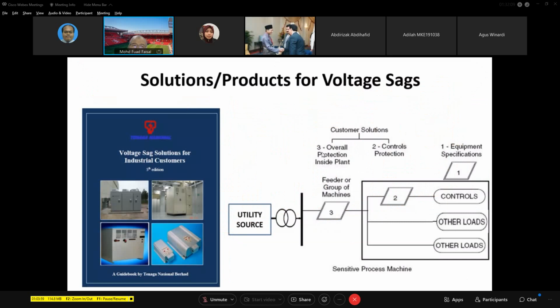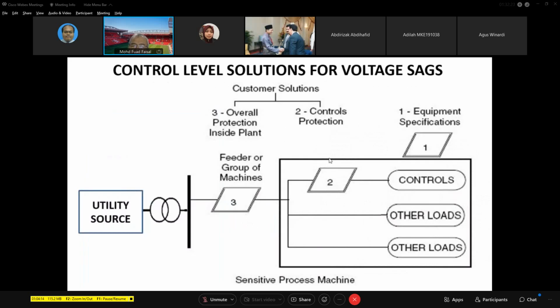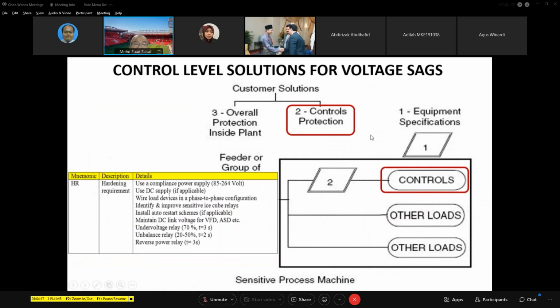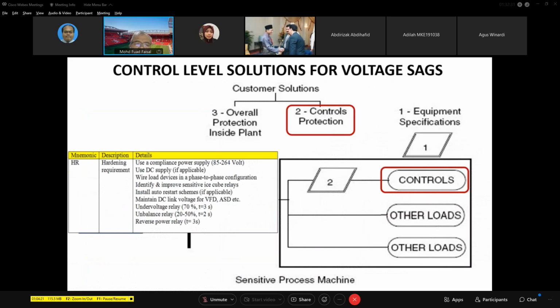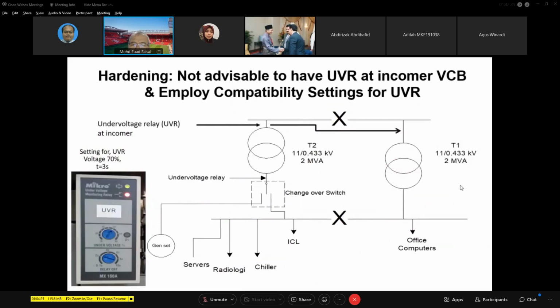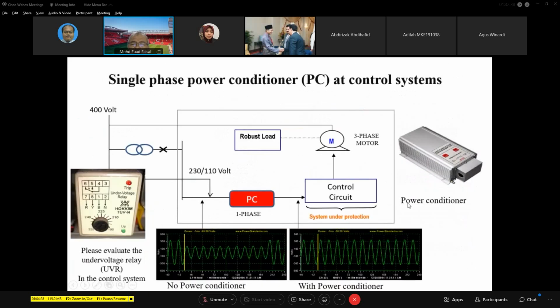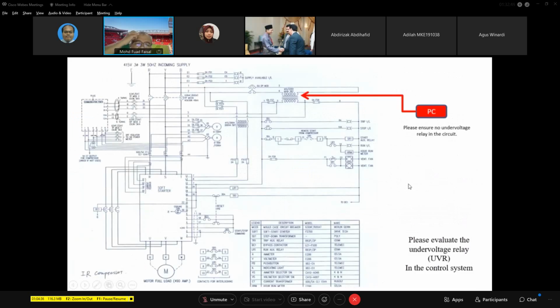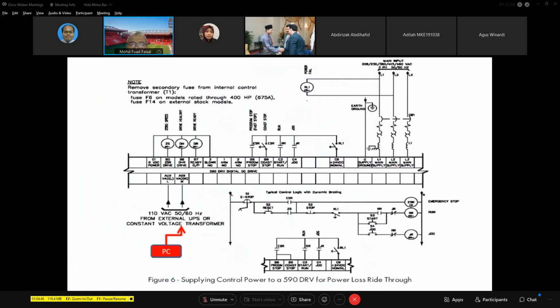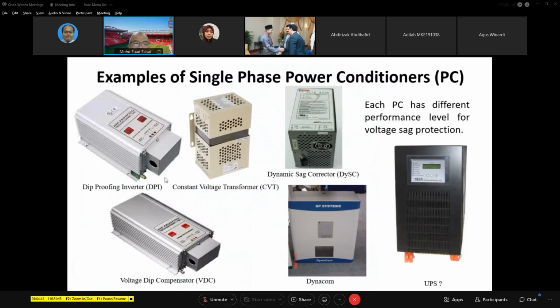Okay, to move forward on PQ, TNB has prepared a few guidebooks. This example is on voltage sag. This guidebook explains to the customer what must be done. Equipment must follow specification, control and protection must be done, overall immunity must be done. So we focus in a little bit more detail, explaining to the customer what needs to be implemented on their side. Then we explain the use of a power conditioner to protect the equipment, and we go into more detail about the wiring requirements for single phase and three phase. In our guidebook we also prepare the solution, or the additive, that needs to be installed at the customer side.